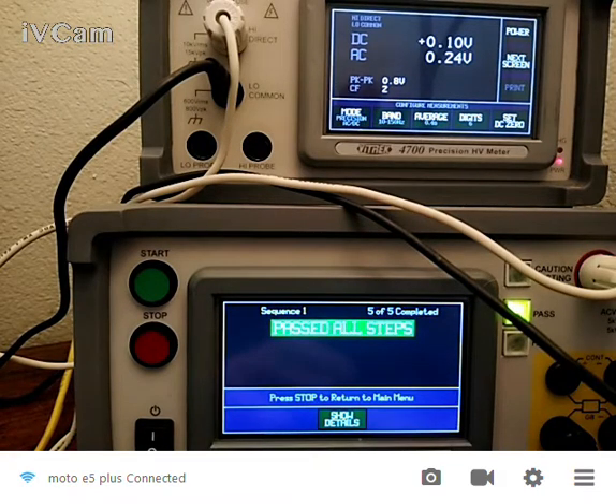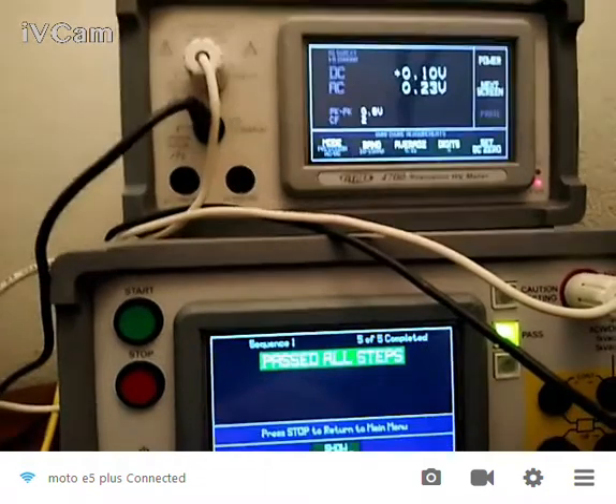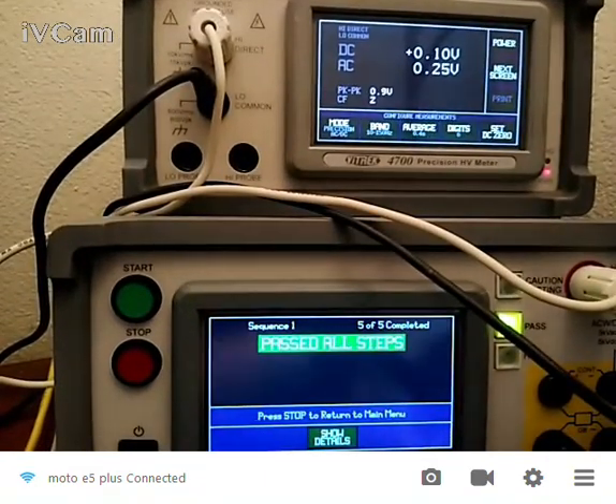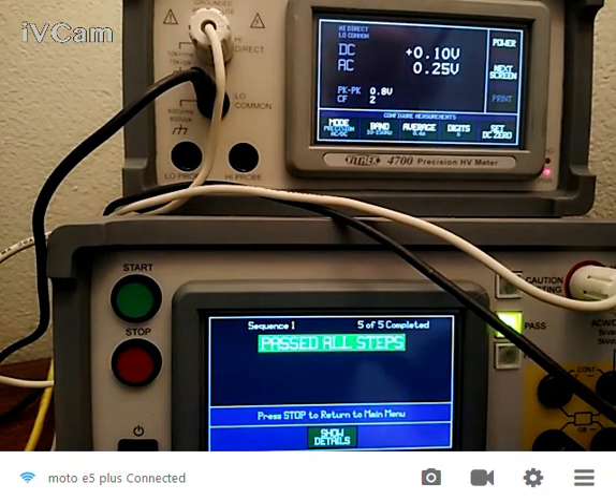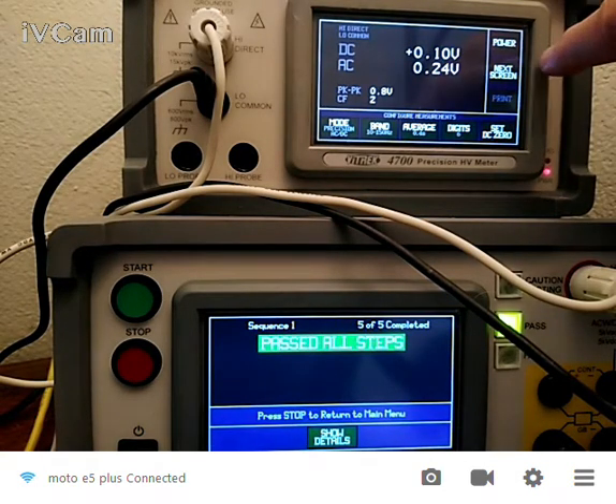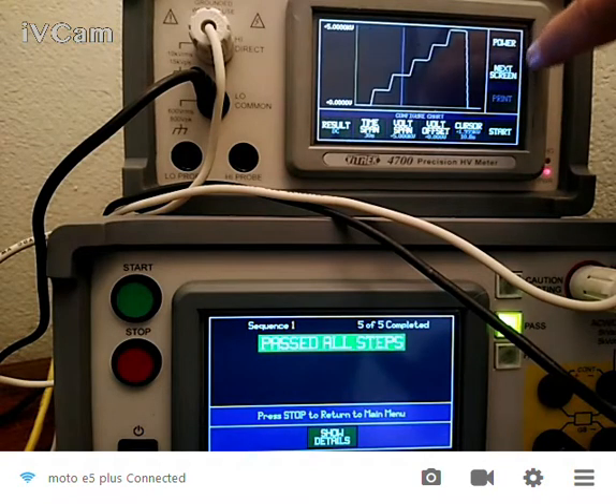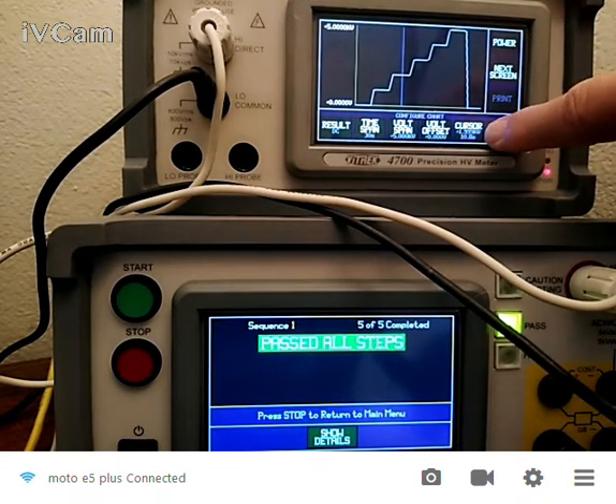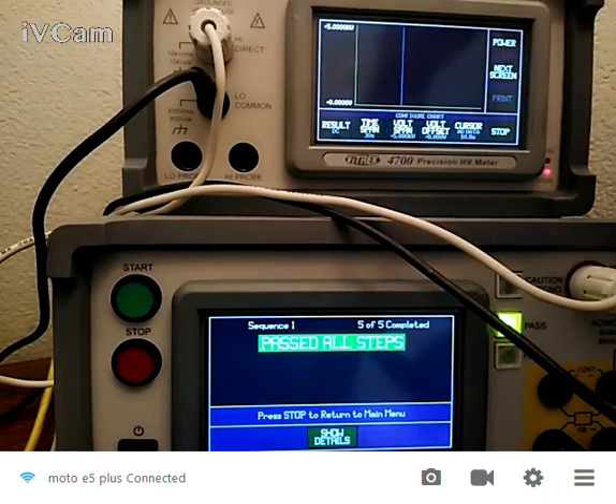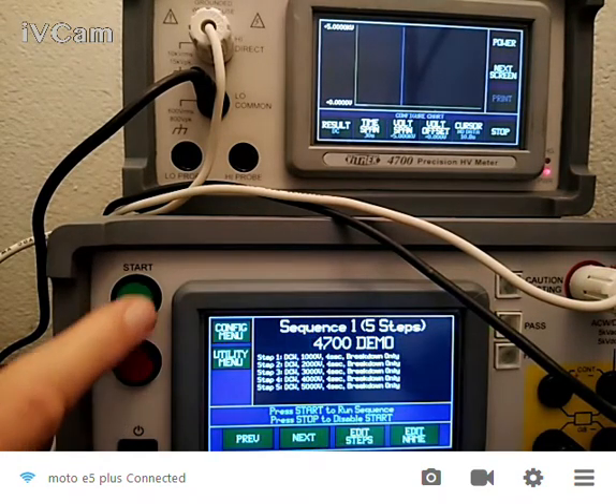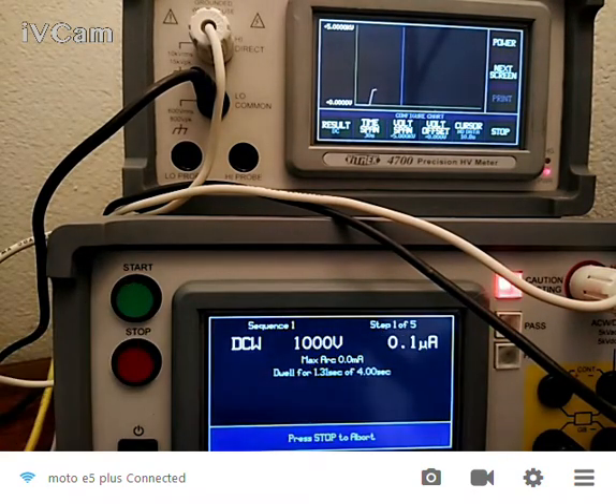So that's the basics of using it. It's pretty simple. It's also highly accurate. 2 countries actually use this as their primary standard, and it's really about the only high voltage meter on the market. Now, if I go on over to my next screen, I'm going to hit Start and Auto. And what you're going to see, I'm going to run the test again, is that it can also chart the trend in voltages over time. So you can do things like look at linearity of a device as you do calibration, which I think is quite handy.